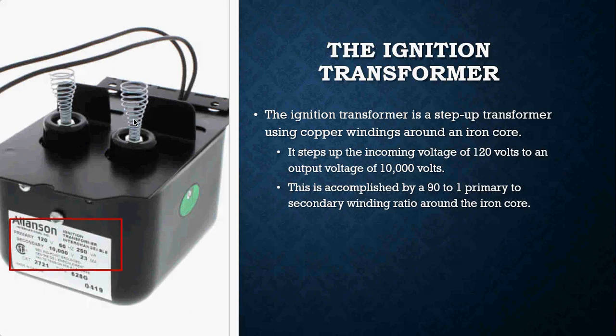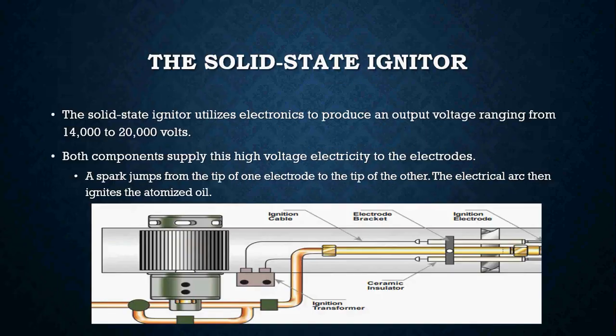So it's important to look at the nameplate on the ignition transformer to see what type of secondary voltage you're dealing with, and also the volt amps and milliamps ratings on there, which I will discuss in a minute. It steps the voltage up to 10,000 volts with about a 90-to-1 winding ratio between the primary and secondary winding wrapped around that iron core.